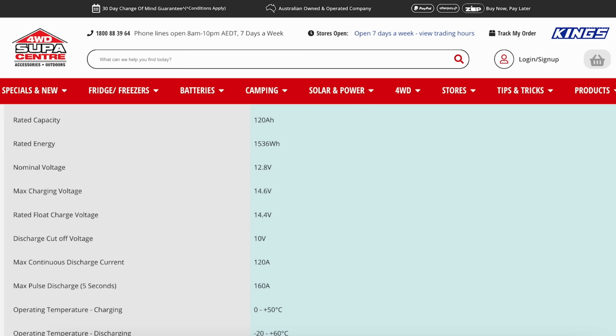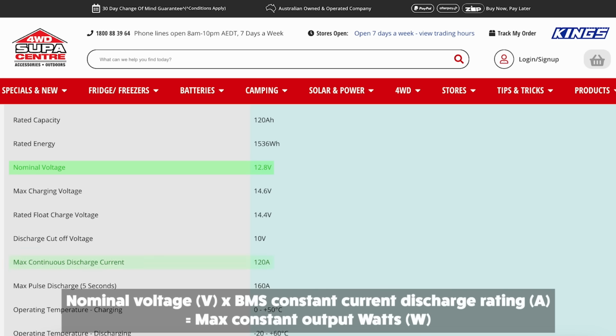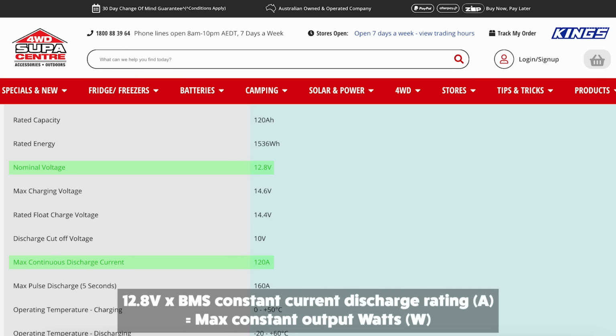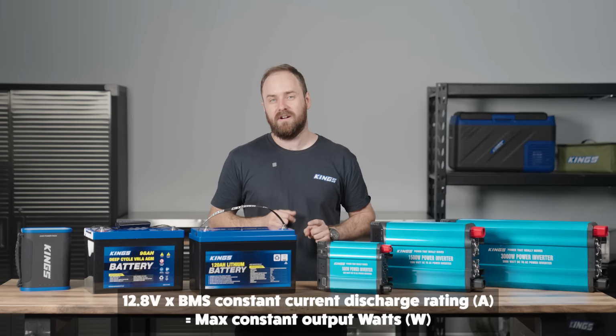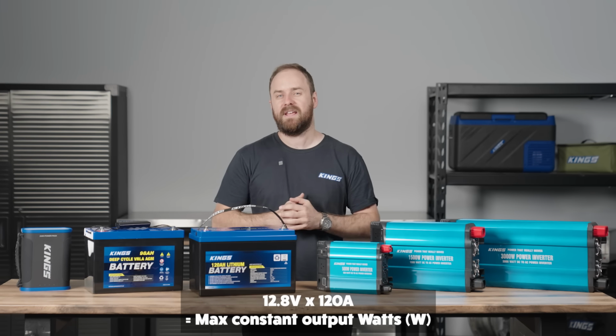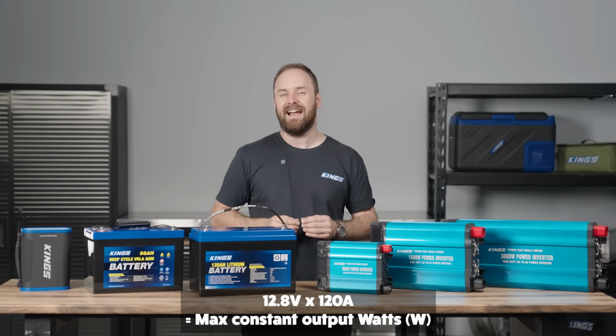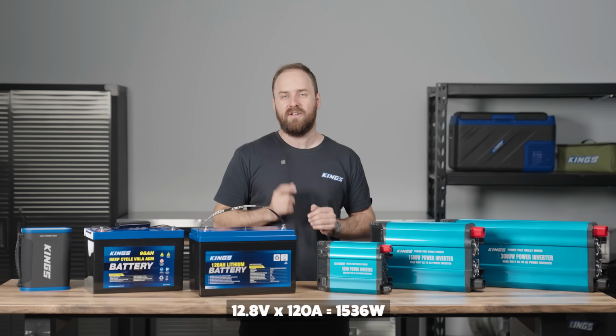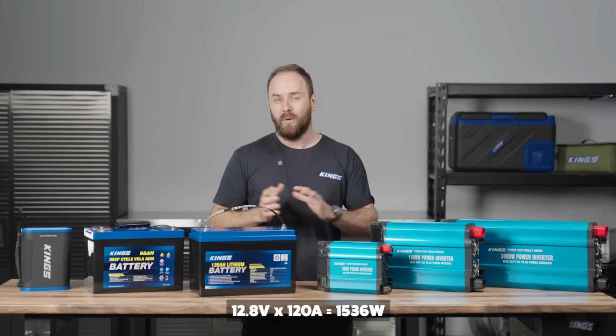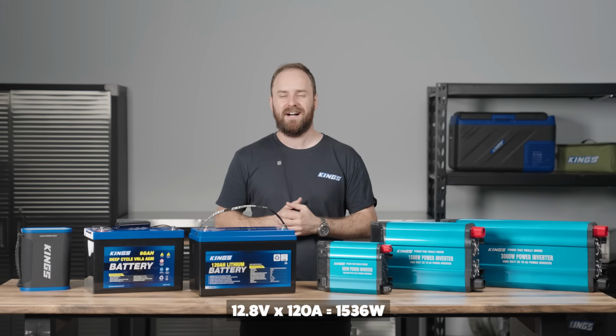The way this is calculated is by multiplying the battery's nominal voltage by its BMS's constant current discharge rating. So in case of the 120 amp hour lithium, the nominal voltage is 12.8 volts and the BMS constant current discharge rating is 120 amps. Multiply those together and you get 1536 watts, meaning it's suitable for up to a 1500 watt inverter.